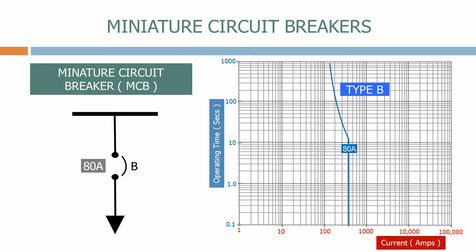The main difference between fuses and MCBs is that when the current gets to a set level they trip with a fixed time delay. As we can see for this 80 amp type B MCB this is defined at just over 400 amps.